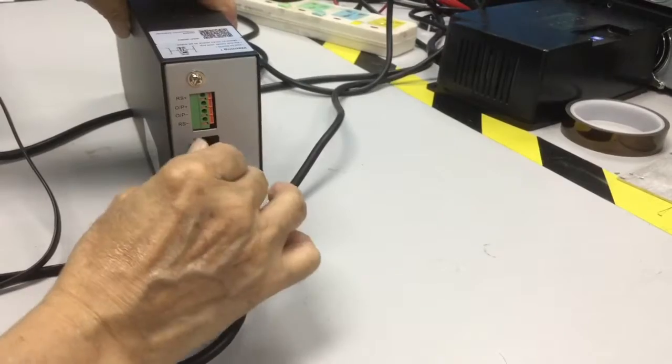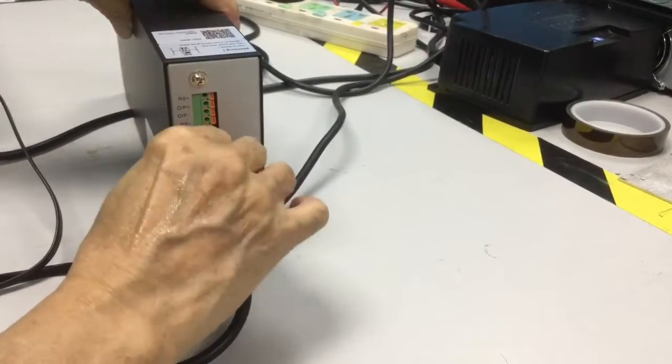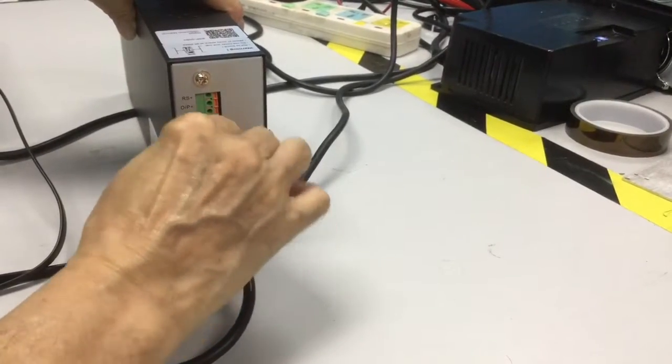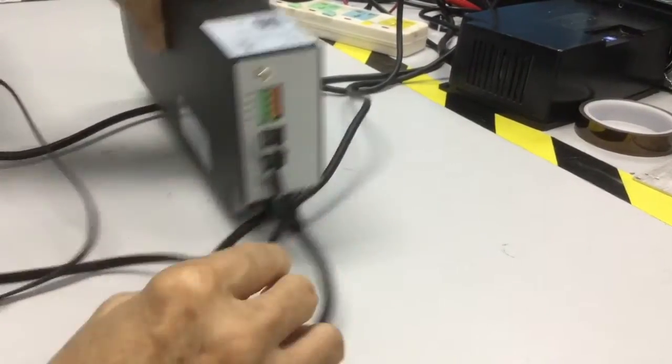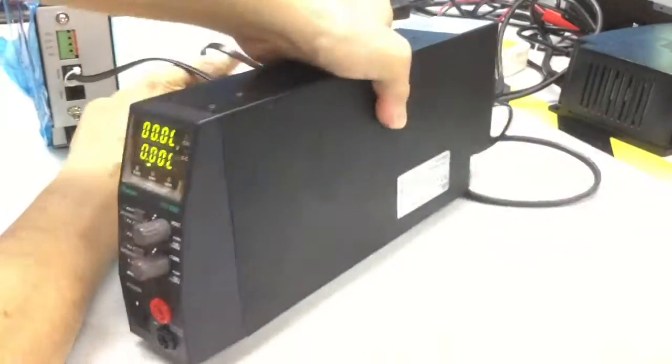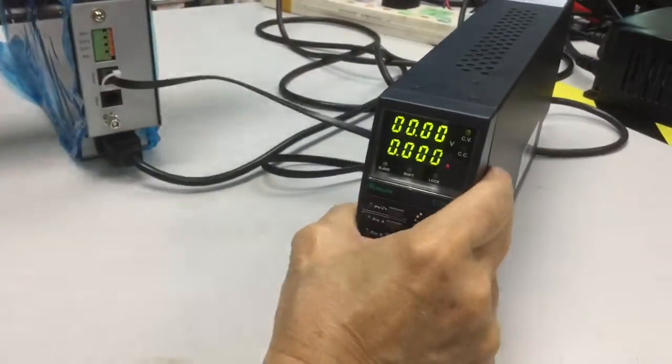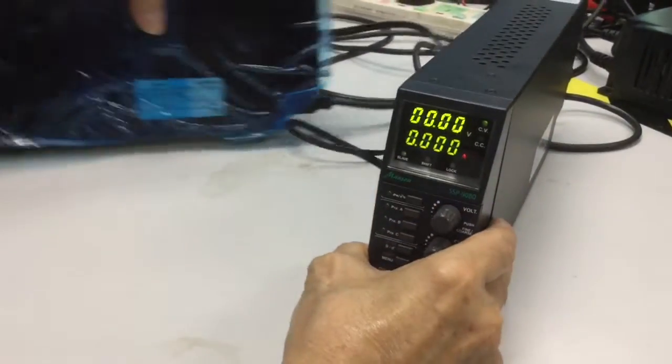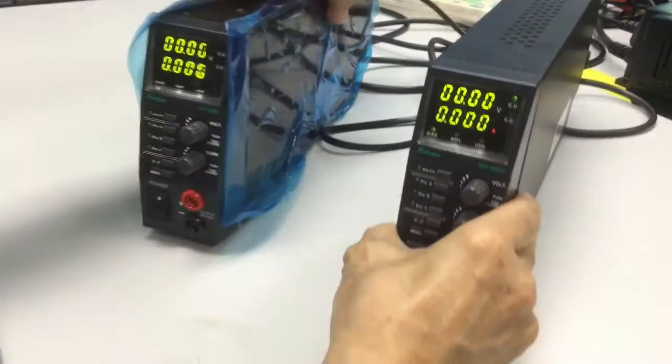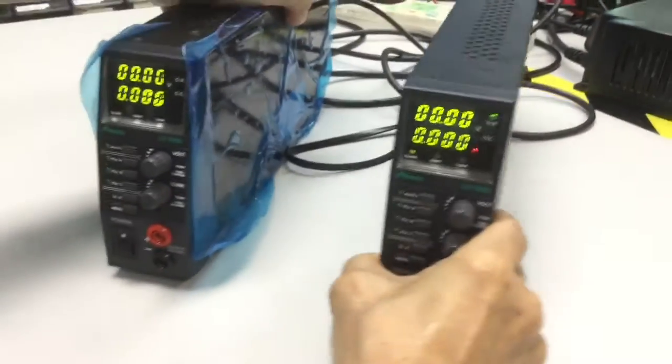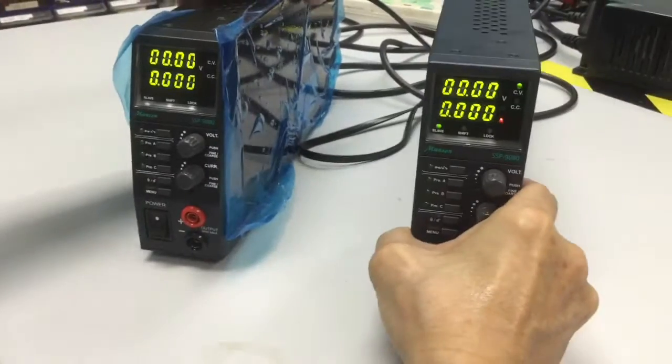And don't forget to put the termination at the end, at the last slave unit. Since we have two units, this is the slave unit, and this is the master unit.